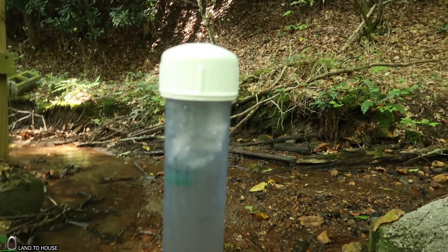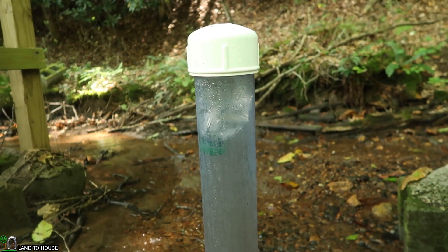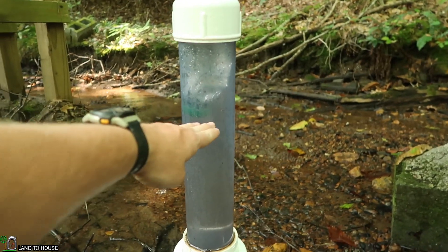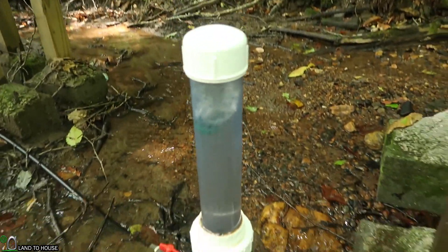Let me show you. See how there's no air in the top of this tank? You can see the water bottle in there pulsing. The water should be somewhere around this point here, but it's not. So a fill material goes in there to give that air space.